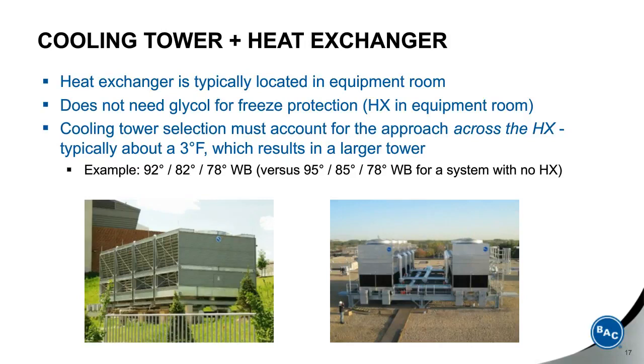In a traditional open loop system, you're designing for 95-degree hot water, say 85-degree off the cooling tower at, say, a 78-degree wet bulb with no heat exchanger in the system. To get 85-degree water back to the tower with a 3-degree approach across the heat exchanger, you'd have to have conditions of 92-degree hot water, 82-degree leaving water off the tower at the 78-degree wet bulb. So you basically have a closer approach on the cooling tower. You go from 7 degrees, which is the leaving fluid temperature minus the wet bulb, to an approach of 4 degrees, which is 82 degrees to 78. So the tower does grow in size in these cases.